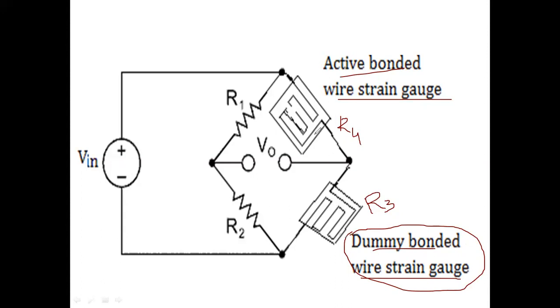Once the strain or stress is applied to the active bonded gauge, the bridge will become unbalanced. Yes, sir. To bring the bridge back to the balanced condition, we are using the dummy bonded wire strain gauge. At the initial condition, we have to set the bridge to be in balanced condition - so to bring the balanced condition, the dummy bonded wire strain gauge is used, making the bridge balanced here now.